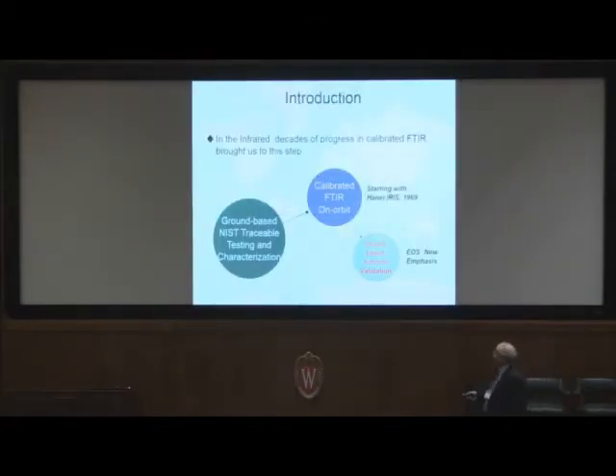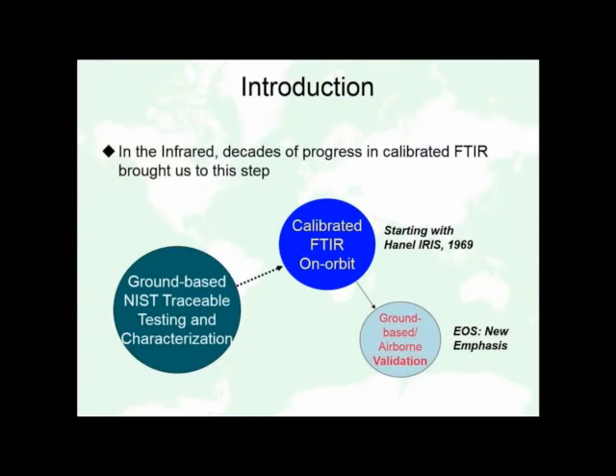Hank presented this yesterday, and it represents sort of where we were up until the point where we started all this CLARREO work, where you do ground-based calibration of your instrument that goes to orbit with standards that are traceable to NIST. But once you're on orbit, there's nothing you can do anymore. You're basically relying on the fact that things don't drift. You can do periodic checks with a ground-based validation, but that's periodic. Sometimes it's very difficult to apply what you would learn in this validation to making any corrections up there.